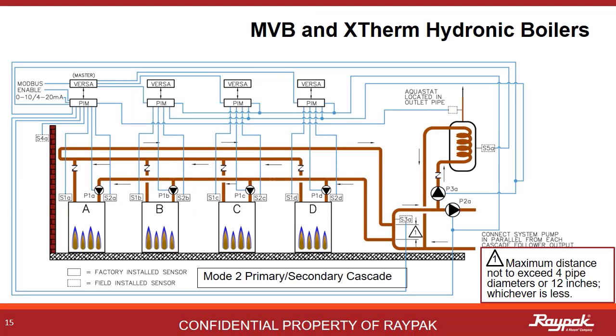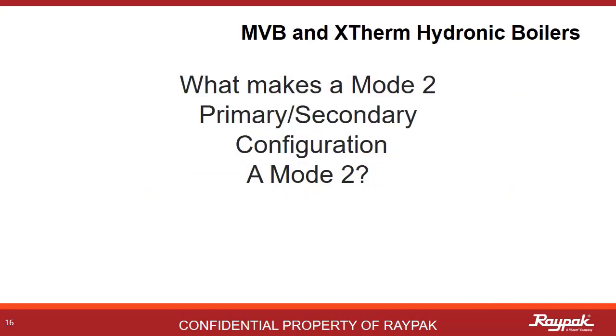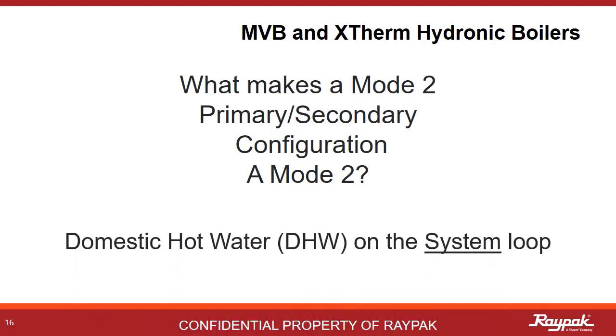Mode 2 is also possible in cascade. As with the single boiler system, the indirect domestic hot water tank is out on the system loop. When in cascade, there can be only one master boiler — the A boiler. The other boilers are the follower boilers. Always apply reverse return logic to plumbing cascaded systems — the first boiler out to the system is the last in line on the return. What makes a Mode 2 primary-secondary a Mode 2? You have an indirect domestic hot water system on the system loop.